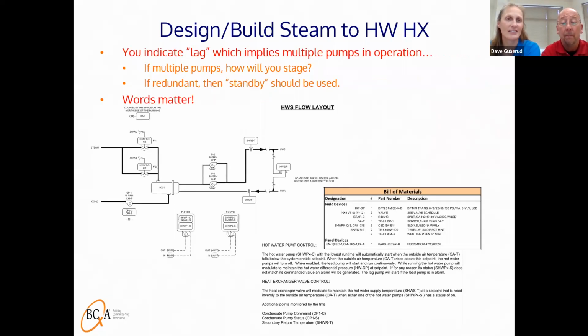So in the sequence, you can see that they indicate lead/lag for the pump, which implies multiple pumps in operation. However, if there's multiple pumps, then do you indicate how they're going to stage? How will you bring on the lag pump? How will you turn off the lag pump? How will you address a failure? Or if they're redundant, then the word should be changed to standby. So, we say words matter. So having a clear understanding of what the intent is helpful.